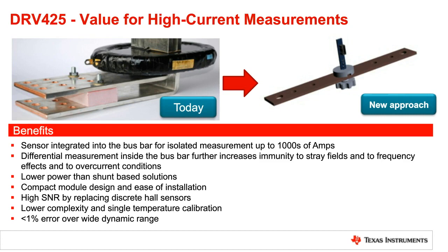We can do a few extra things with this. One is we can increase immunity by using two devices, so any stray fields are effectively canceled out, and we're only measuring the fields generated by the bus bar. Since the amount of electronics required is significantly reduced, it has a much lower power requirement. And one of the main things is just how compact this is.